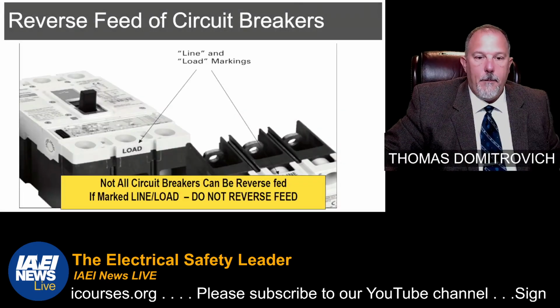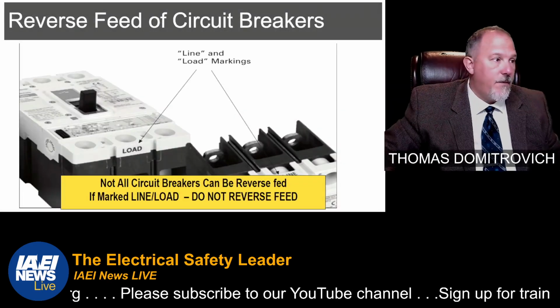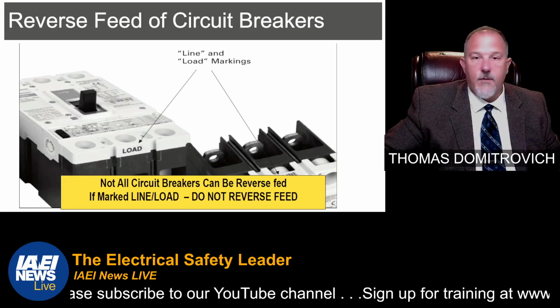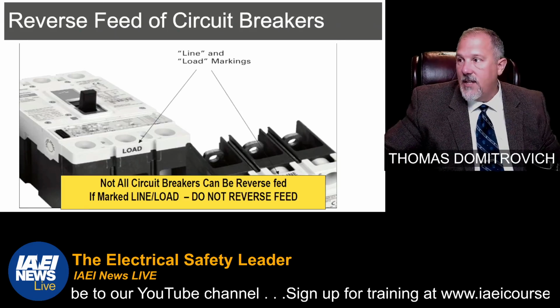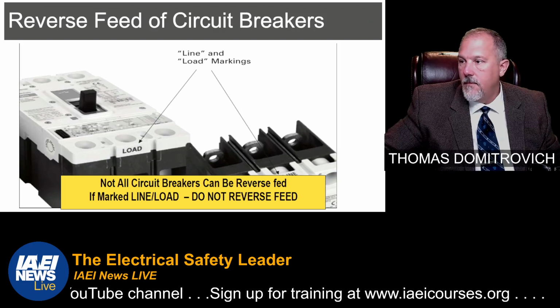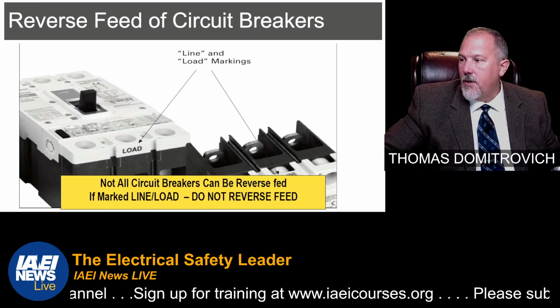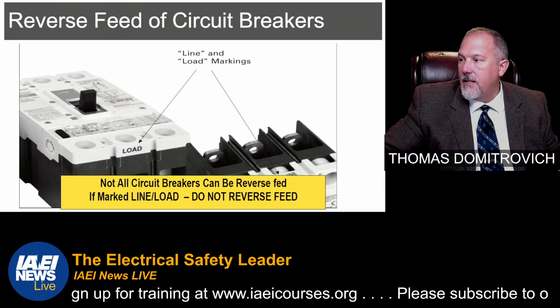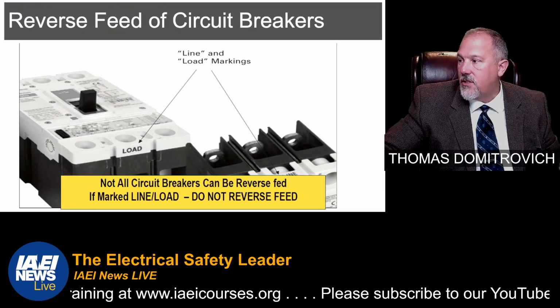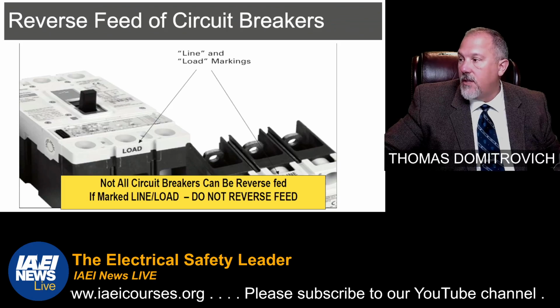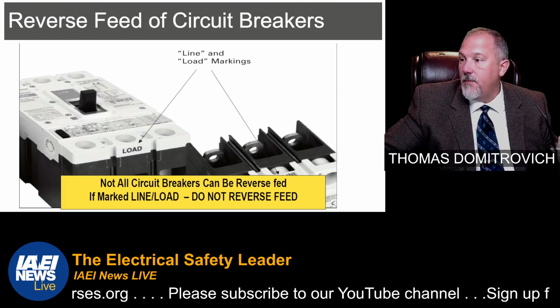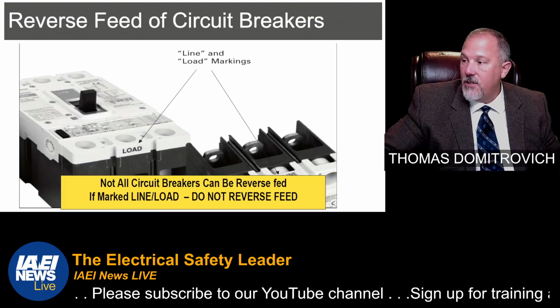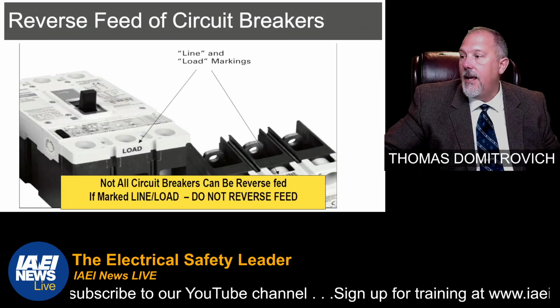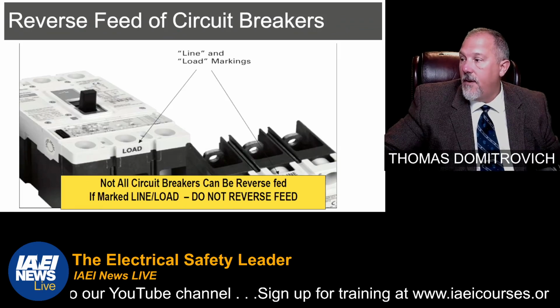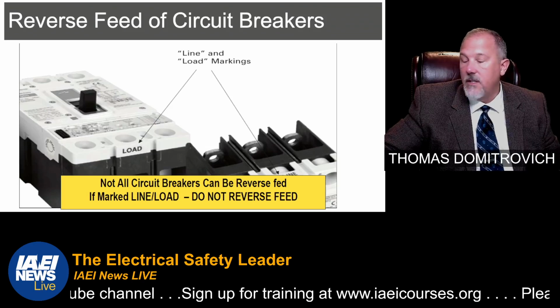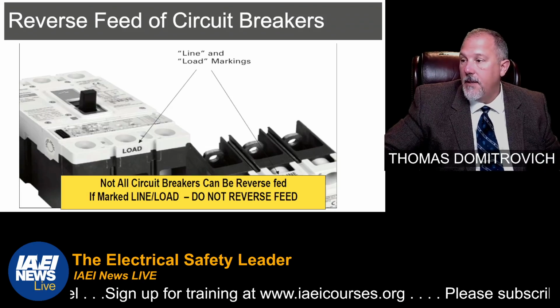All right, so supplied through a transformer, something that is often missed. Oh, reverse circuit for reverse feed, backfed devices. This is 408.36(D). It says plug-in type overcurrent protective devices or plug-in type main lug assemblies that are backfed and used to terminate field installed ungrounded supply conductors shall be secured in place by an additional fastener that requires other than a pull to release the device from the mounting means on the panel board. So these are plug-in type, not the bolt-in type.